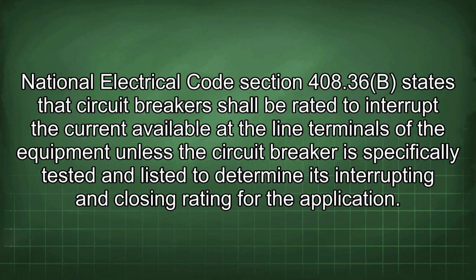National Electrical Code Section 408.36(B) states that circuit breakers shall be rated to interrupt the current available at the line terminals of the equipment unless the circuit breaker is specifically tested and listed to determine its interrupting and closing rating for the application.